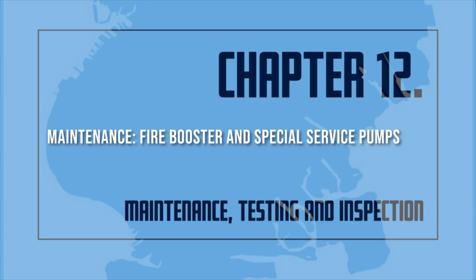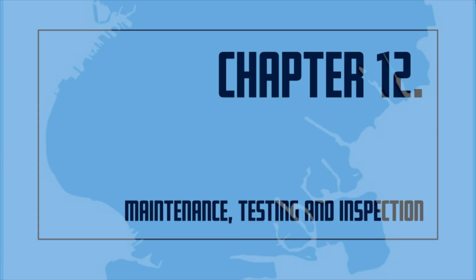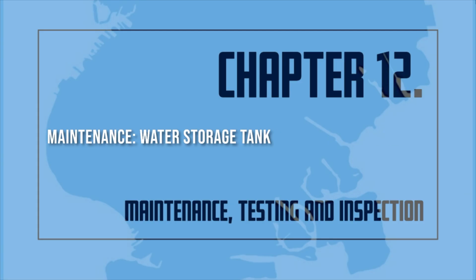B. Fire booster and special service pumps. A preventative maintenance program shall be maintained on all components of the pump assembly in accordance with the manufacturer's recommendations. If there is no manufacturer's recommendations for preventative maintenance, use Table 8.5.3 of the NFPA No. 25, 2002.